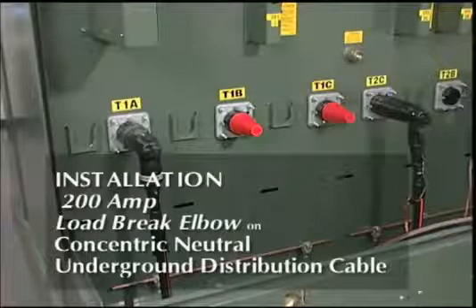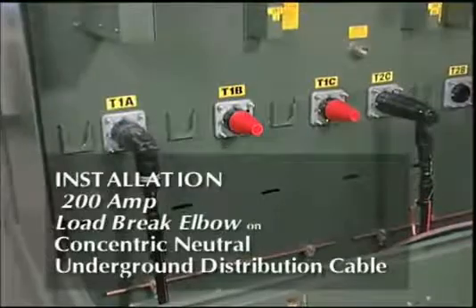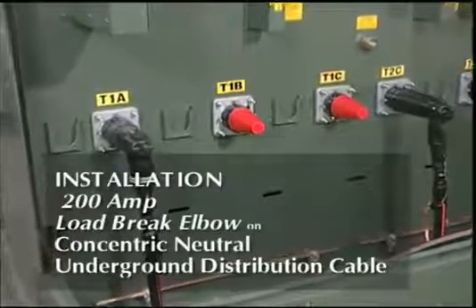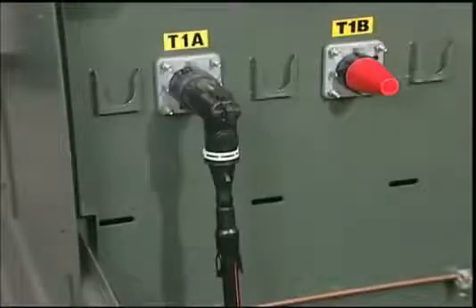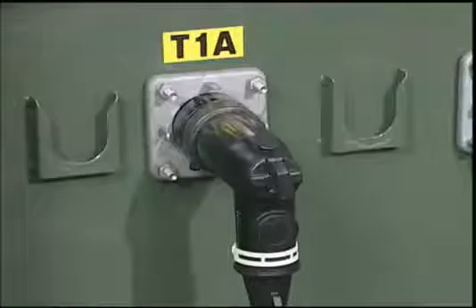This shows the installation of a 15 kV 200 amp load break elbow with optional integral jacket seal on a typical concentric neutral underground distribution cable. This video shows the installation of a 15 kV elbow. Installations of 15, 25, and 35 kV elbows with and without the integral jacket seal are similar.